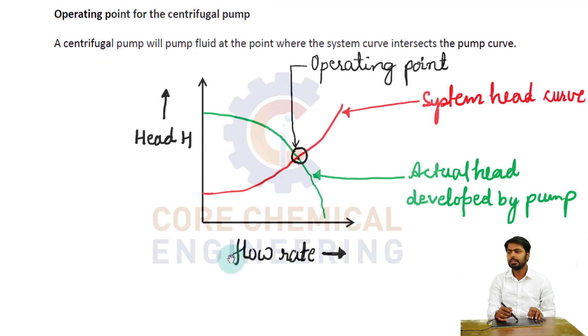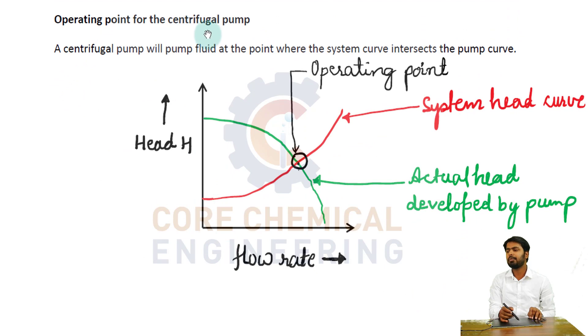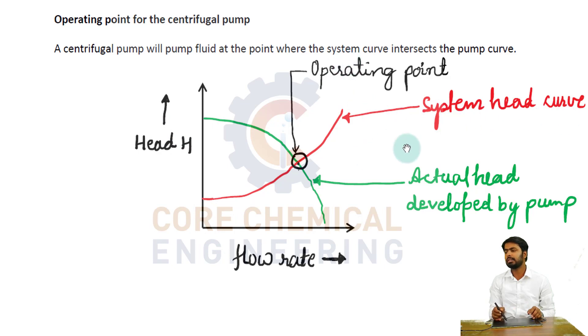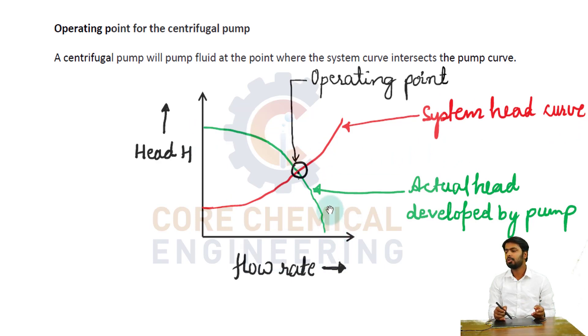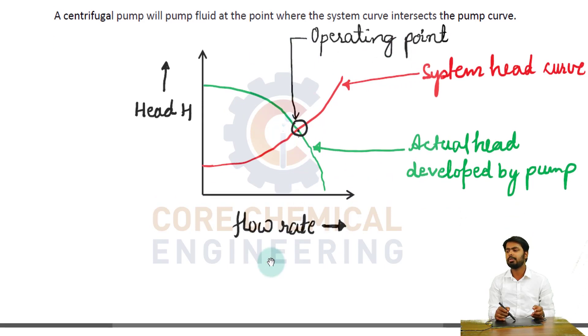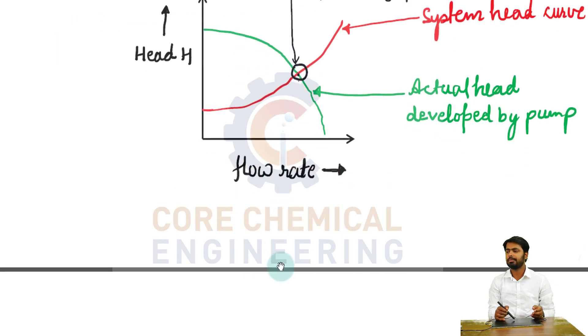Now the long-awaited question: the operating point for the centrifugal pump. If we draw both graphs on a single plot — the system head curve and the head developed by the pump — the point where both curves intersect is the operating point for the centrifugal pump.